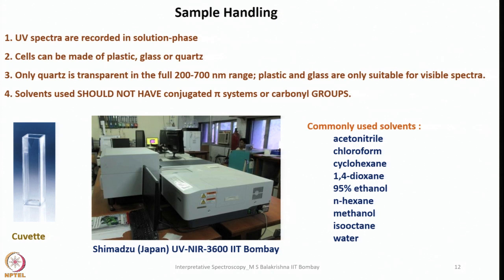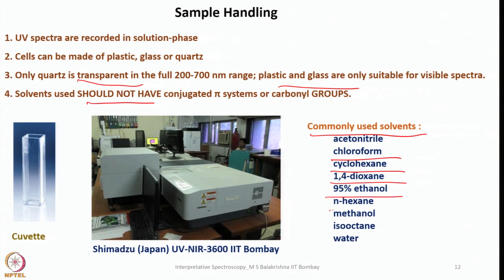Sample handling is very important. UV spectra are recorded in solution phase; cells can be made of plastic, glass, or quartz — but preferably quartz should be used because only quartz is transparent in the full 200 to 700 nanometer range, while plastic and glass are only suitable for visible spectra. Solvents should not have a conjugated pi system, carbonyl groups, or any groups with lone pairs of electrons. Commonly used solvents include acetonitrile, chloroform, cyclohexane, 1,4-dioxane, 95% ethanol, n-hexane, methanol, isooctane, and water — chosen depending on the solubility of the sample.